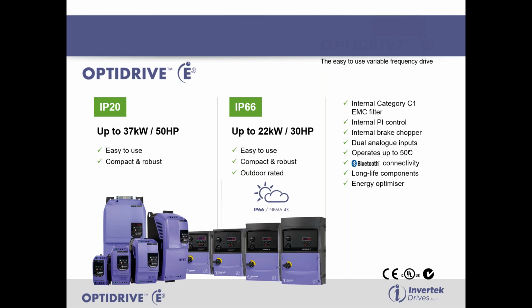So we have a specification that our component suppliers have to reach, a minimum of 50,000 hours. So we have also preventative maintenance plans and those kind of things for the drives to help to keep the lifetime as long as possible. And we also have an inbuilt energy optimizer that can be turned on or off depending on the application.